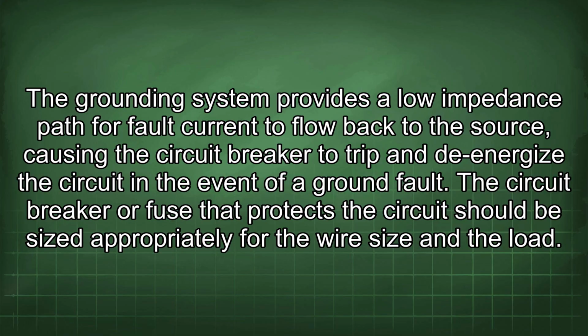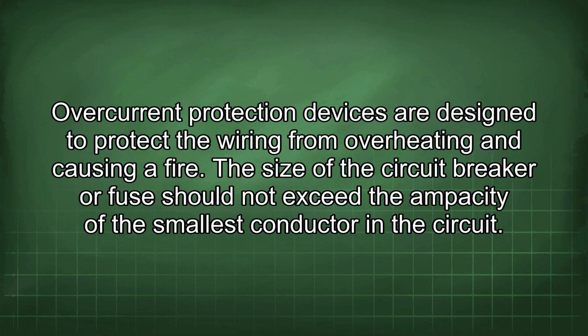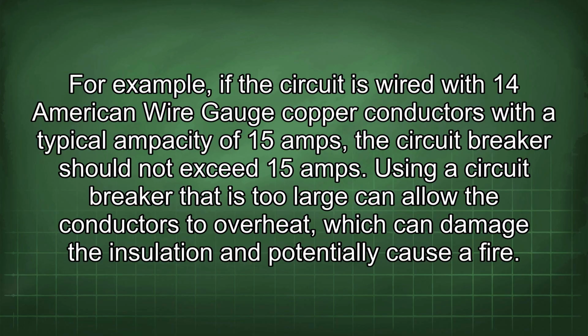The circuit breaker or fuse that protects the circuit should be sized appropriately for the wire size and the load. Overcurrent protection devices are designed to protect the wiring from overheating and causing a fire. The size of the circuit breaker or fuse should not exceed the ampacity of the smallest conductor in the circuit. For example, if the circuit is wired with 14 American wire gauge copper conductors with a typical ampacity of 15 amps, the circuit breaker should not exceed 15 amps. Using a circuit breaker that is too large can allow the conductors to overheat, which can damage the insulation and potentially cause a fire.